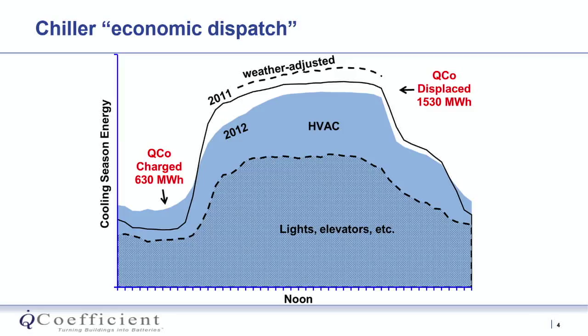You should also know at Willis Tower, we only controlled the temperatures in 13 of 100 floors. They were closer to the base, roughly 20% of the floor space of the building. But controlling 20% of the floor space, I get that kind of performance on the entire building's air conditioning system. So controlling chiller loading at the margin is the goal.